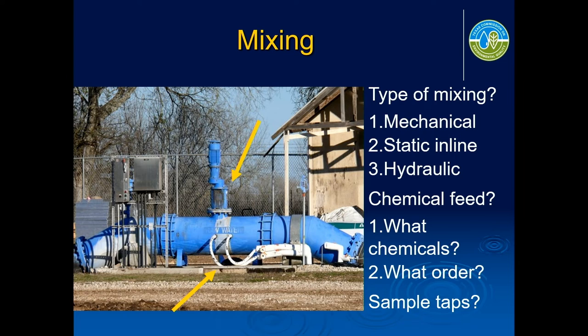Here's an example of a mechanical inline mixer. We're always interested in whether you have a static, mechanical, or hydraulic mixer. This one is in pretty good shape. This particular plant — some of you may recognize it — has clarifier turbidities consistently well below the regulatory requirement for treated water going to town. This plant is optimized, and that operator — an old West Texas guy — does a pretty good job with the water. You can also see injection ports on either side of that mixing system.